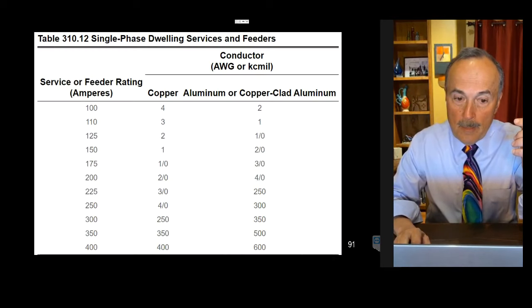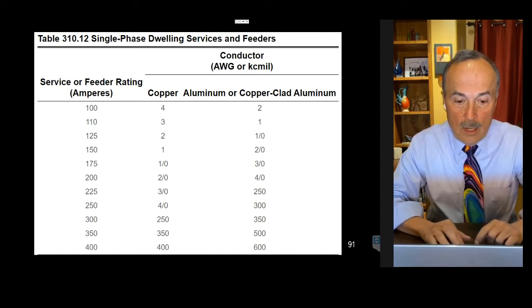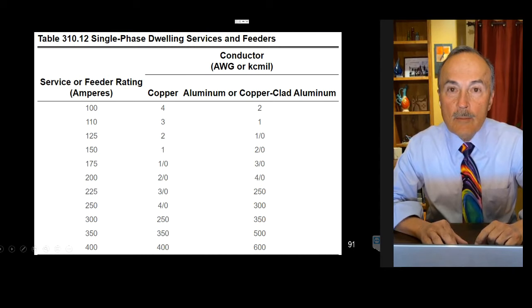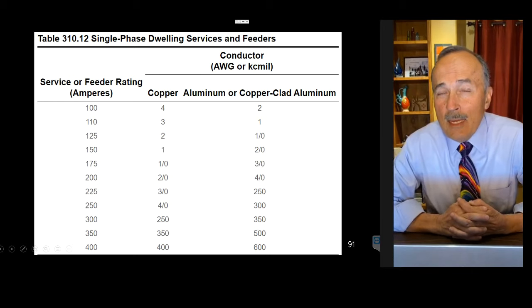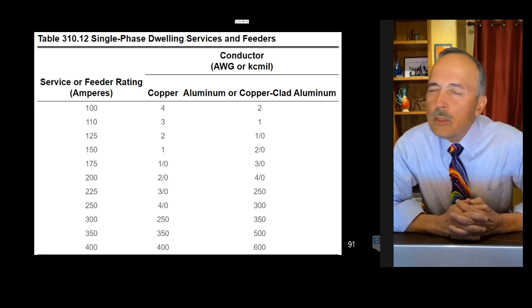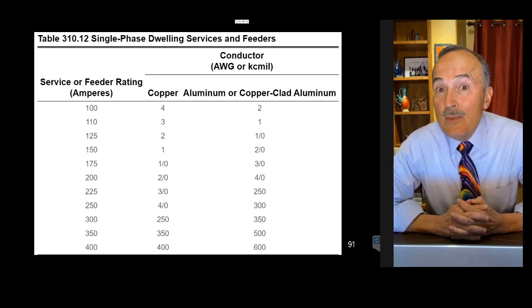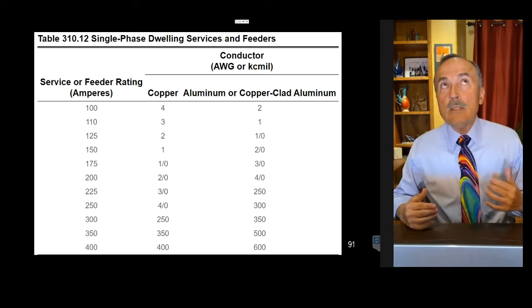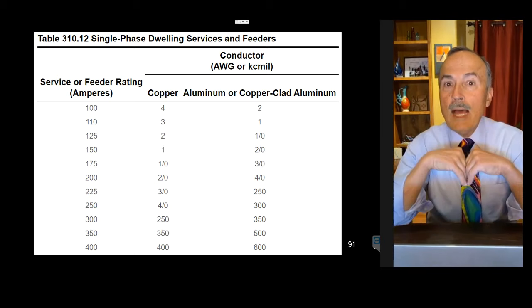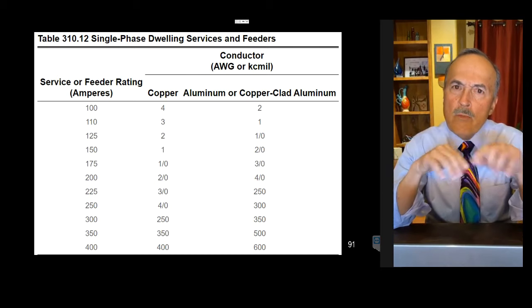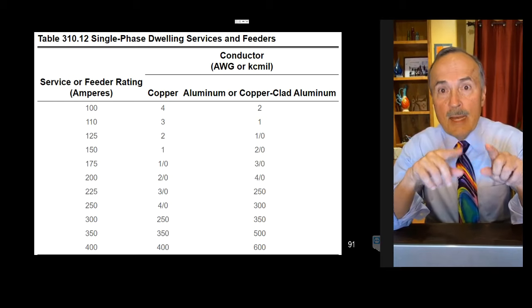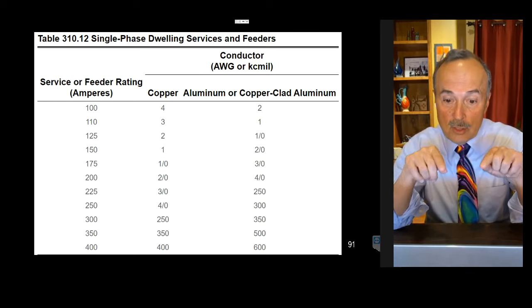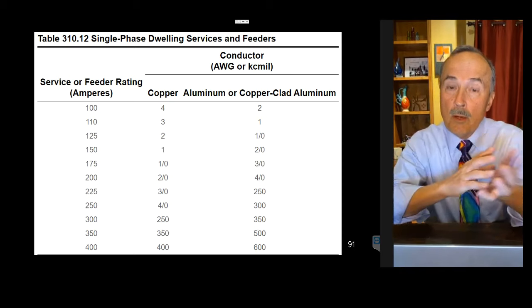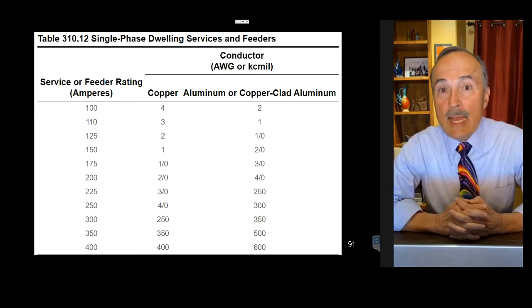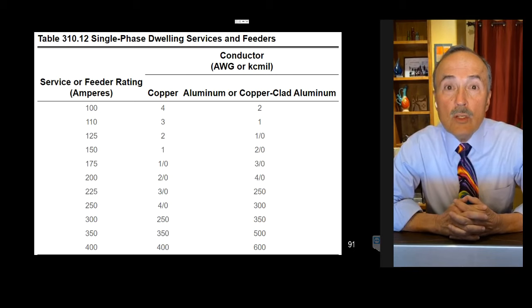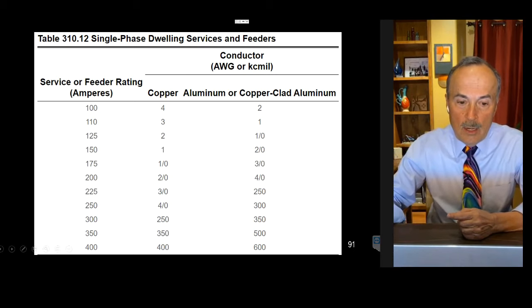I never really thought about this 83%. By the way, this 83% for residential only came about because we used to have a table that told you 400 amp service. Matter of fact, look what it is. It had this table, 400 amp service, 600 kcmil aluminum wire. They took that table out, I can't remember back, 2002, 2005, somewhere in there, maybe 2011. They removed the table and said, we really want to give them an actual mathematical calculation.